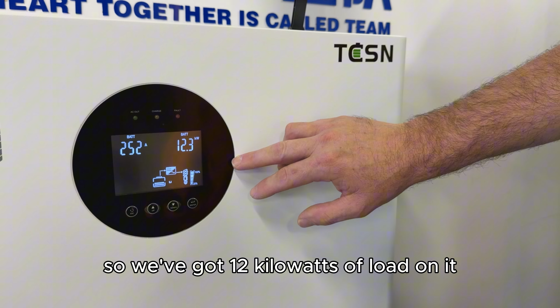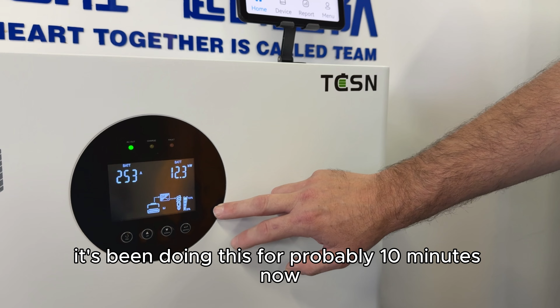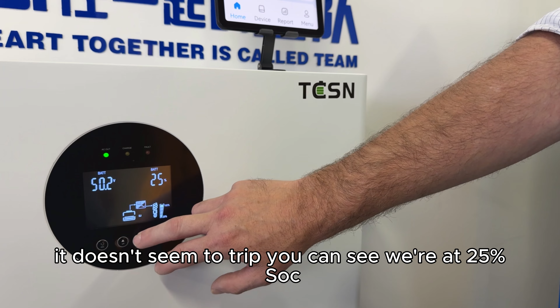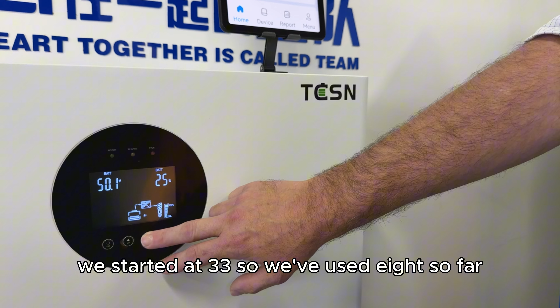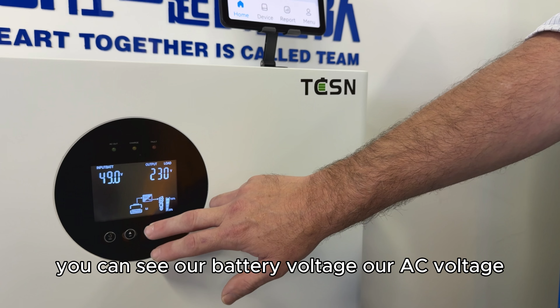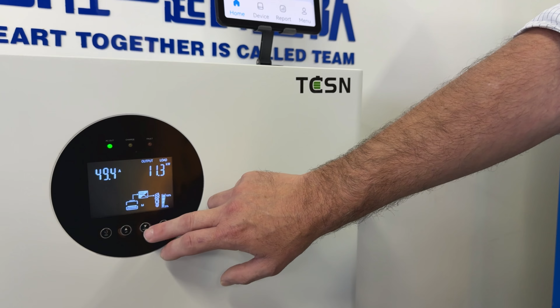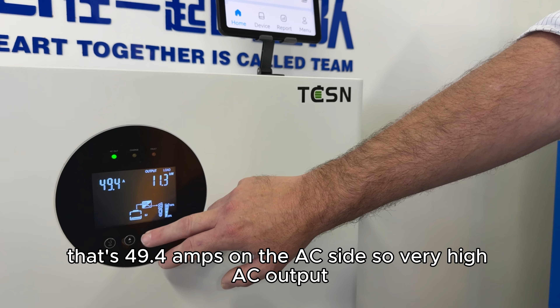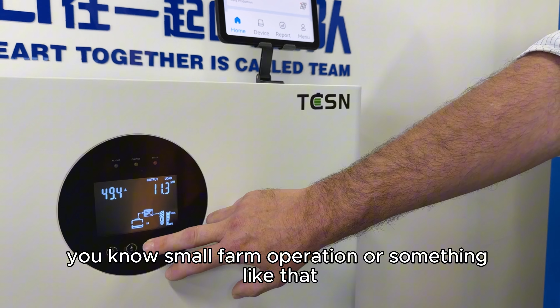At the moment, we're doing a discharge test. So we've got 12 kilowatts of load on it from a resistive load bank, and you can see here we've got 253 amps on the battery side. It's been doing this for probably 10 minutes now, very consistently. It doesn't seem to overload, it doesn't seem to trip. You can see we're at 25% SOC. We started at 33, so we've used 8 so far. You can see our battery voltage, our AC voltage. And that's 49.4 amps on the AC side, so very high AC output, more than enough to run a small house or a small farm operation or something like that.